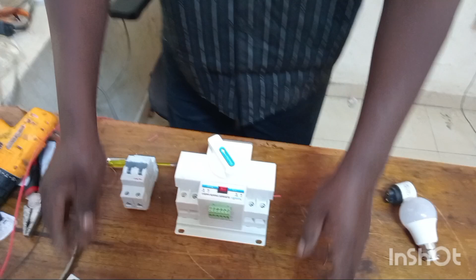So we are going to set it up. This is power from the power company, call it utility, and this is the backup, which is the generator or the solar system, power from the solar. And this third double pole will go to the house. So we start our connection. This is power from the utility.